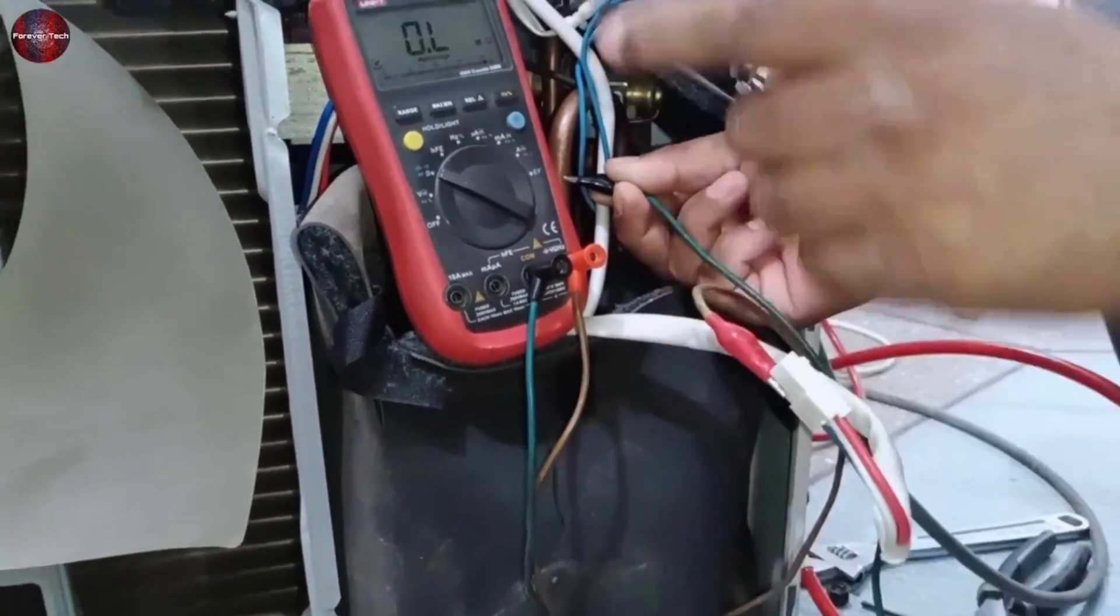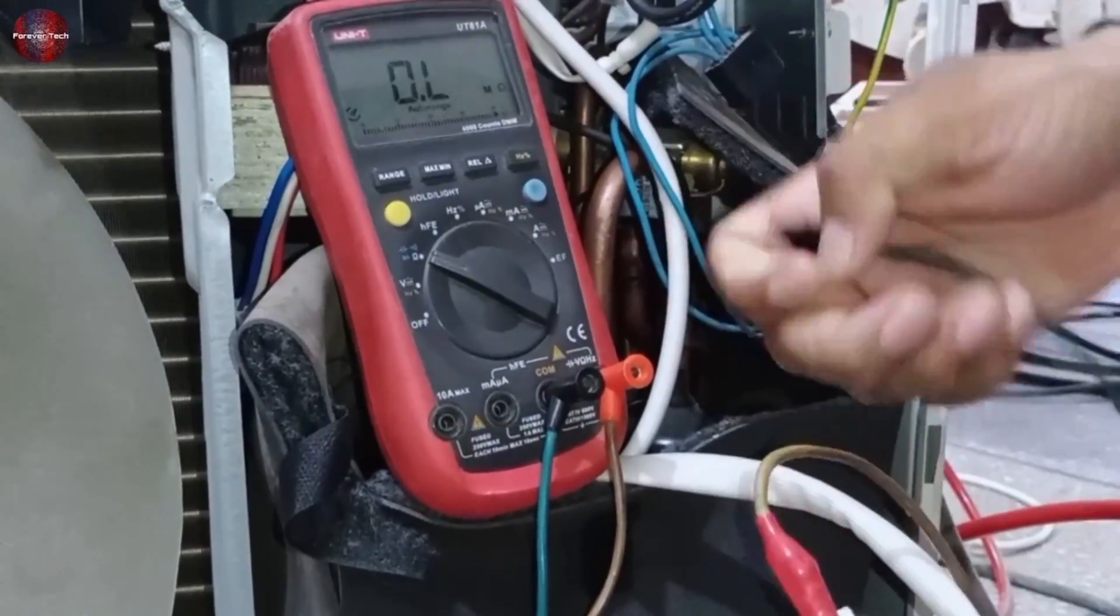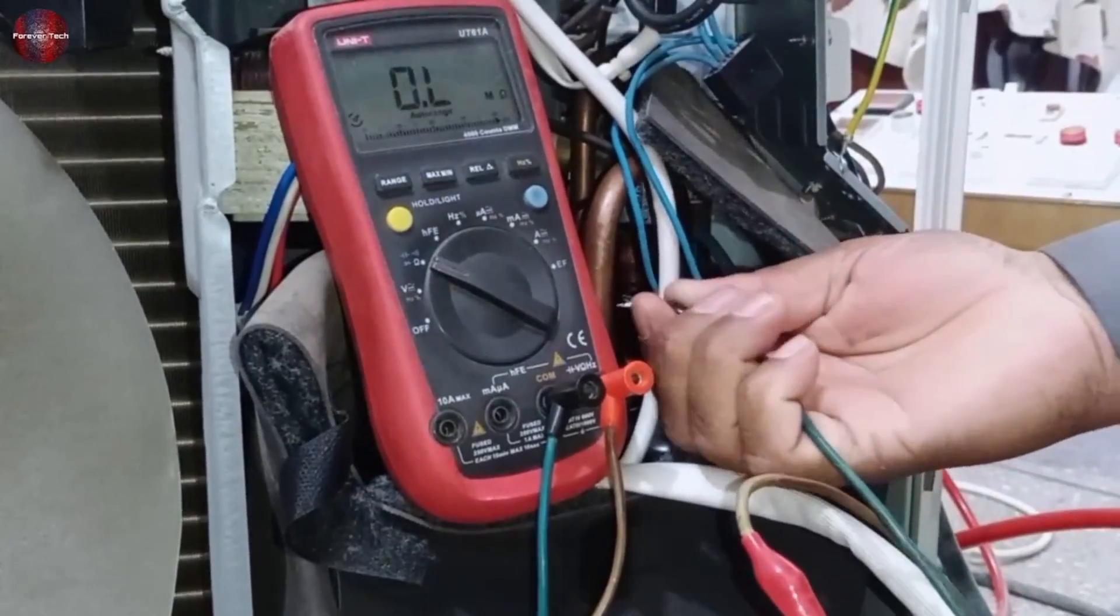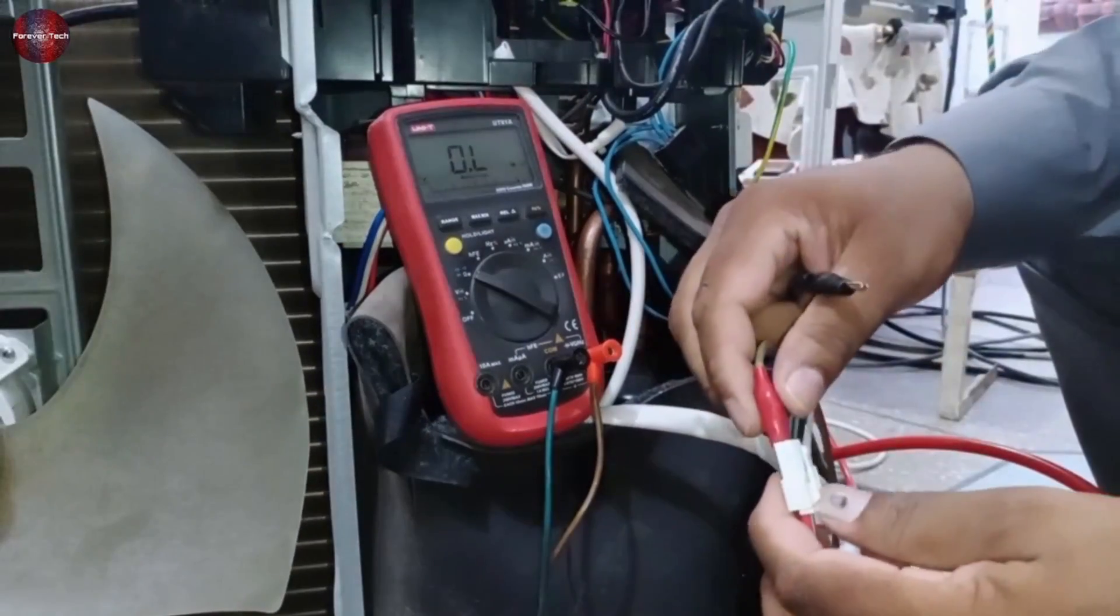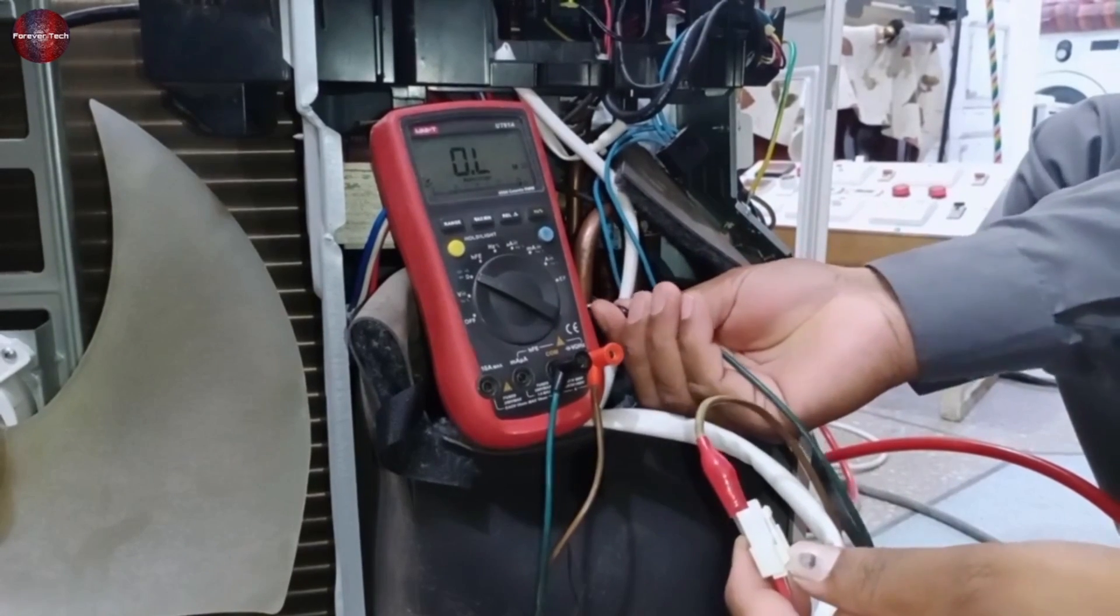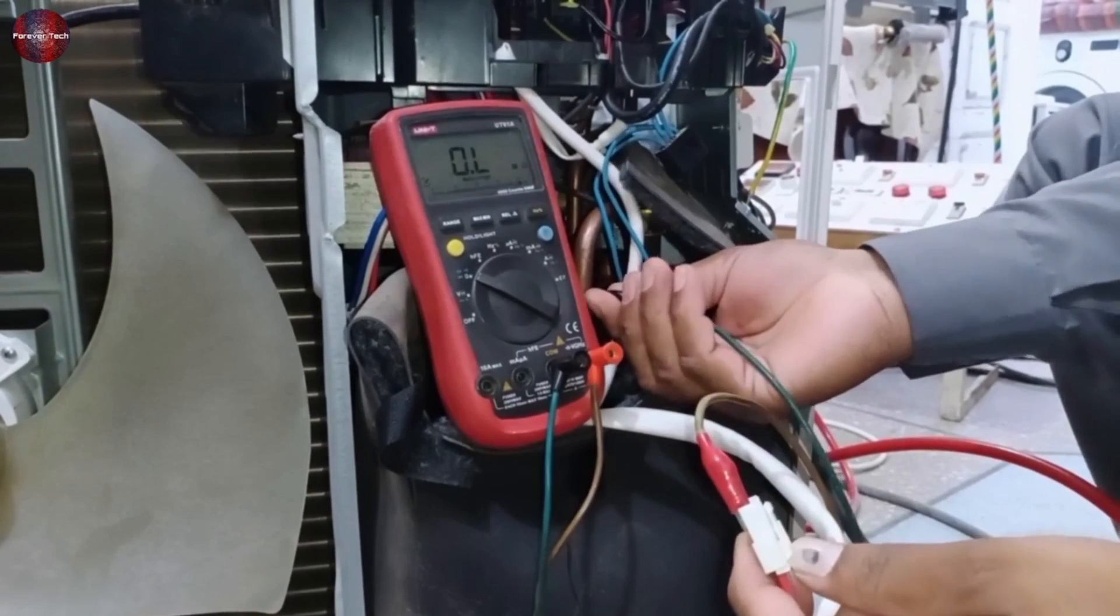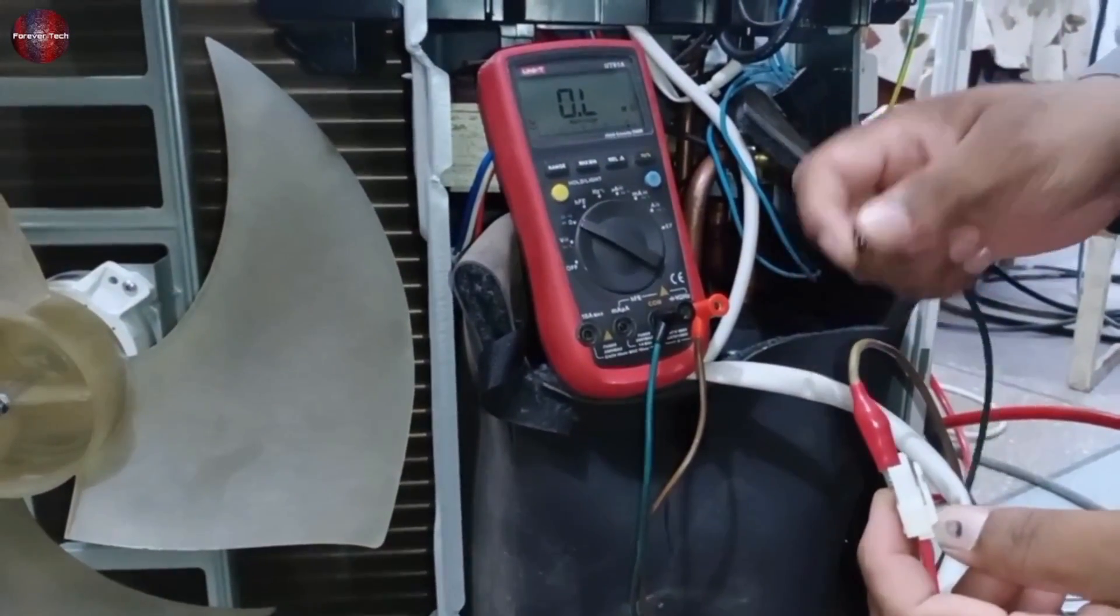See, the multimeter is showing no reading. Same, attach the red probe of the multimeter with the next terminal of the compressor and check the compressor leakage. It also has no reading. In the same way, I checked the third terminal as well. It means that the winding of the compressor is fine and has no leakage or body short inside the compressor.